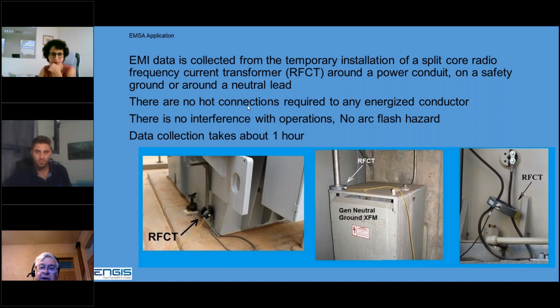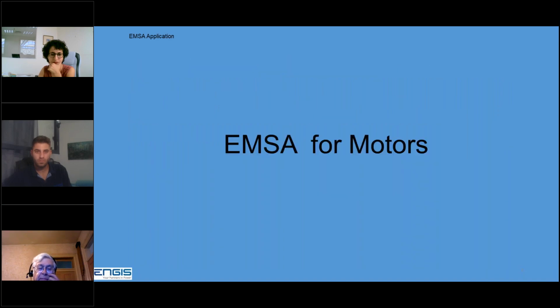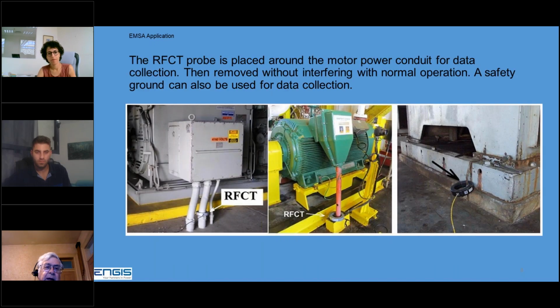No hot connections required to any energized conductor. There's no interference with operations, no arc flash hazard. Data collection takes roughly 1 hour to finish. EMSA is applied for motors. Here the probe is placed around the motor power conduit when it's available. Then you remove it. There's no safety problem, and there's no interfering with normal operations.